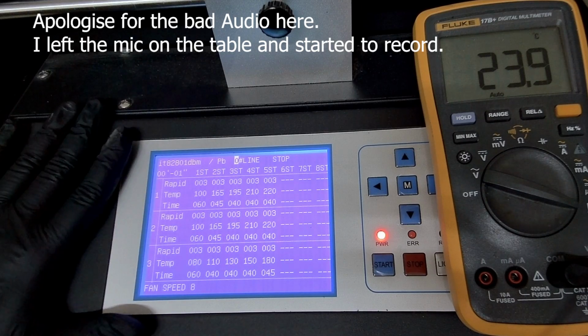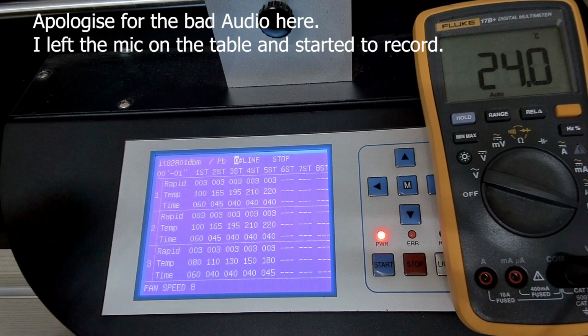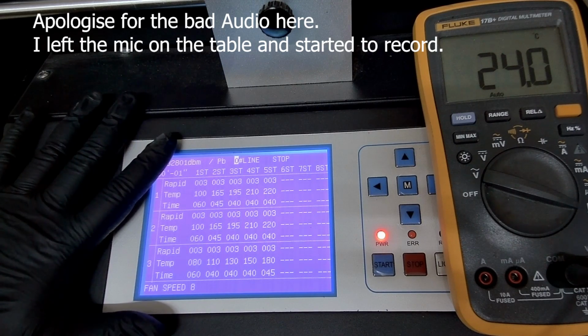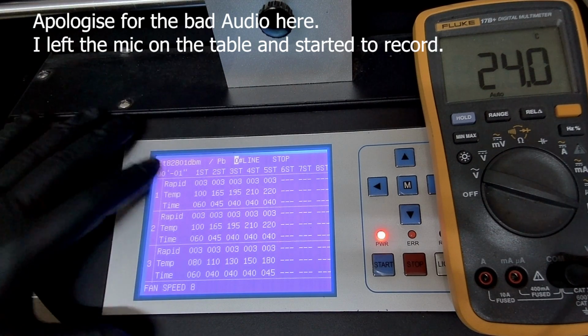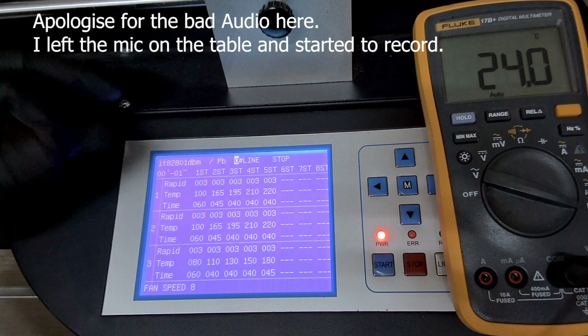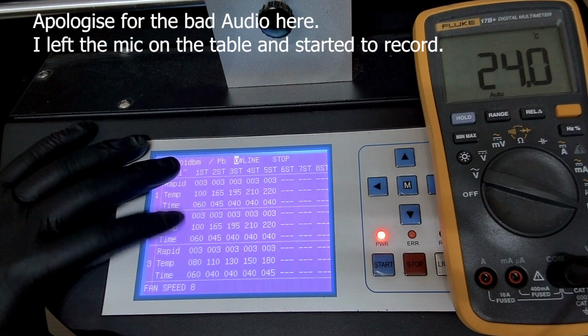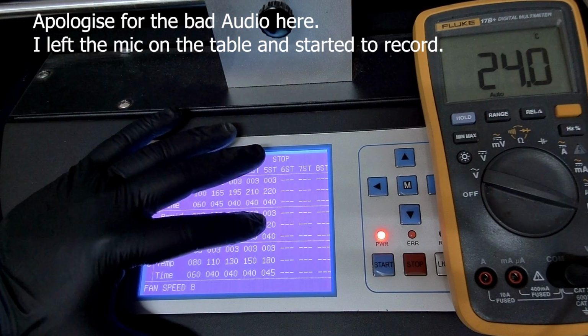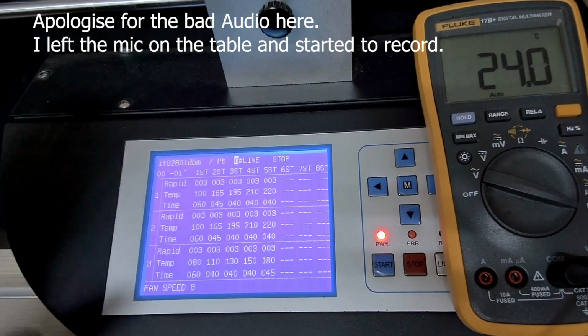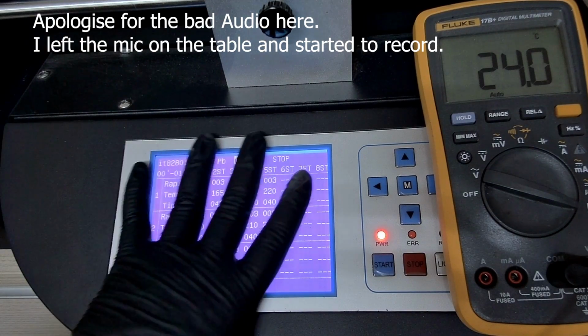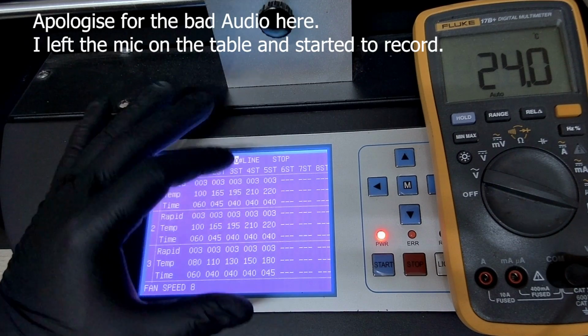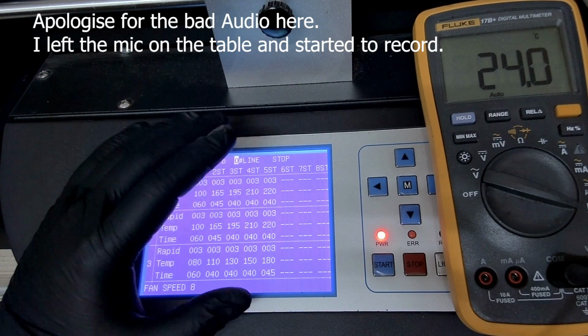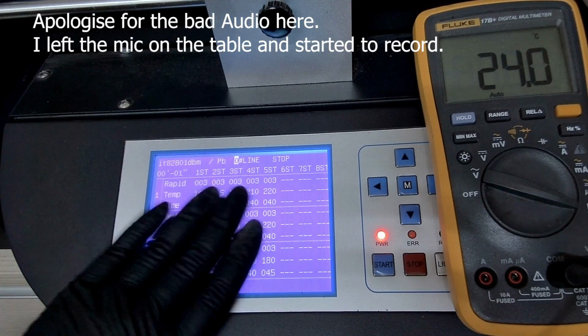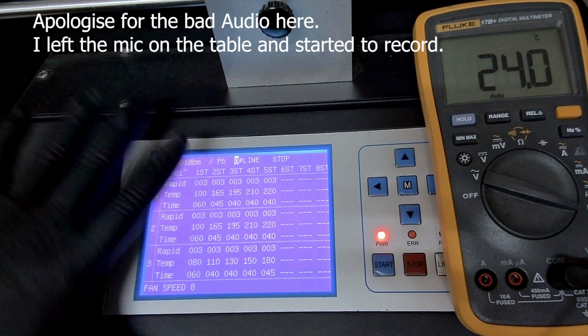For this machine, checking both temperatures: the top temperature is off by 10 degrees when measuring from 100 to 220. The bottom variation ranges from 5 degrees up to 50 degrees. But when measuring the rest of the presets, like 225, 245, and 255, the variation is 60 degrees at the bottom for this machine.